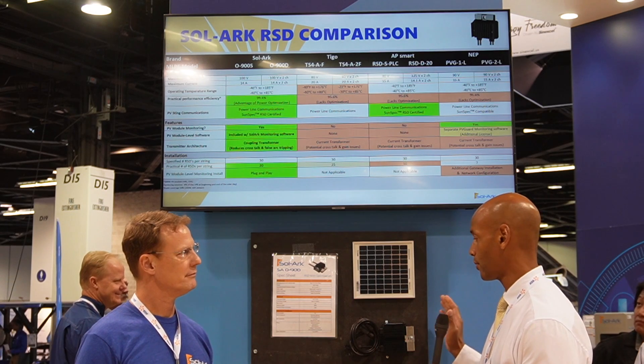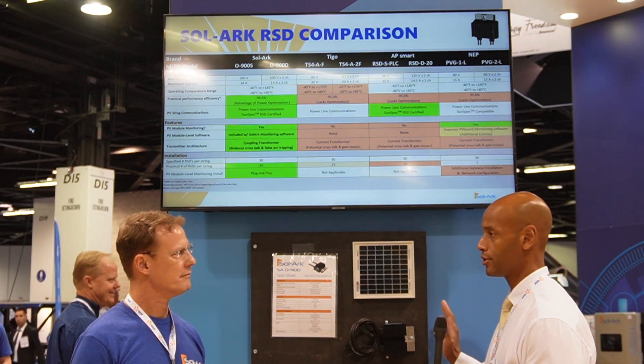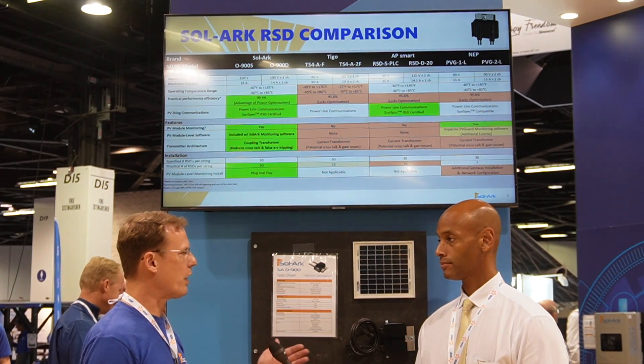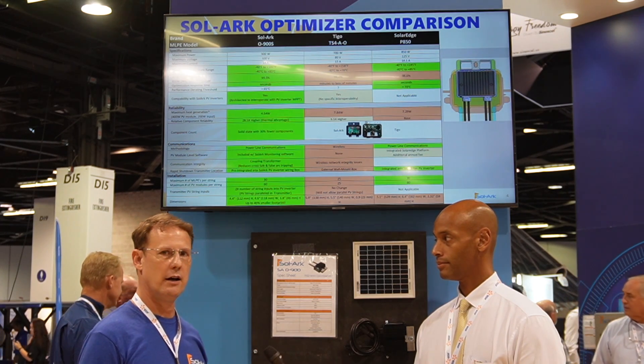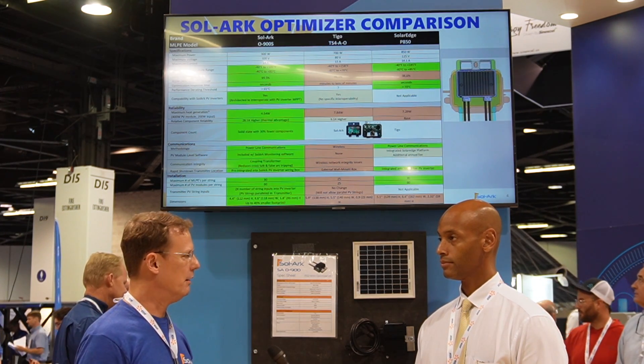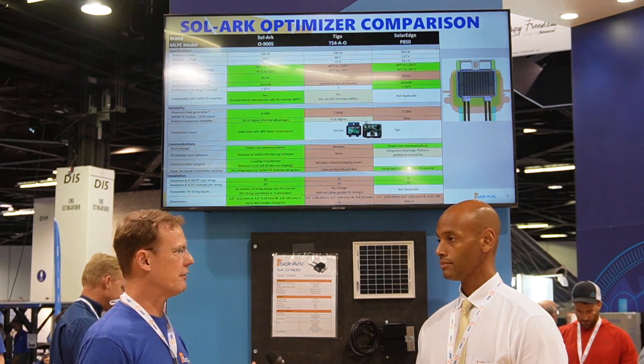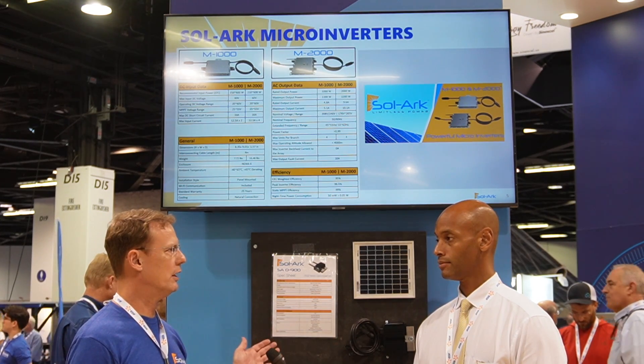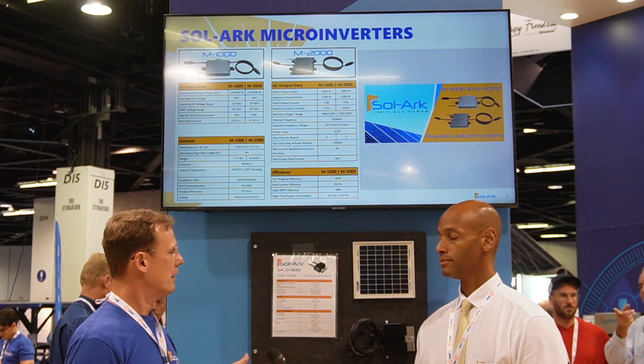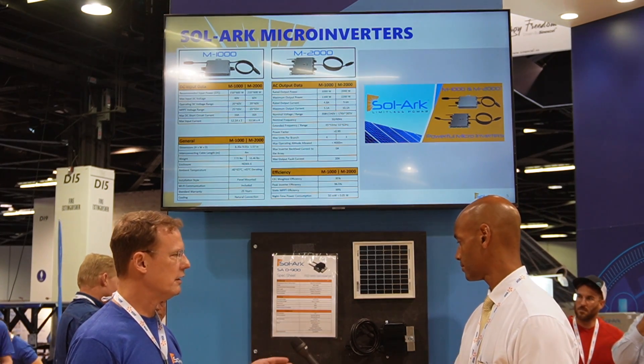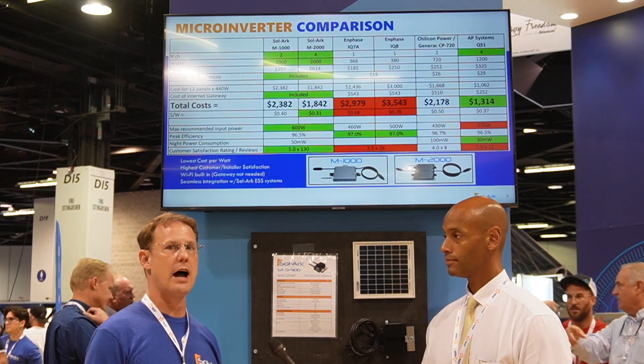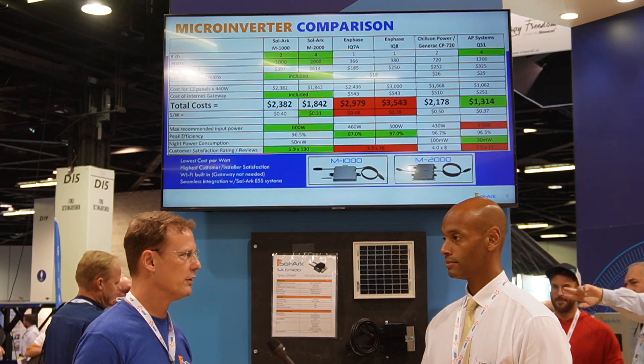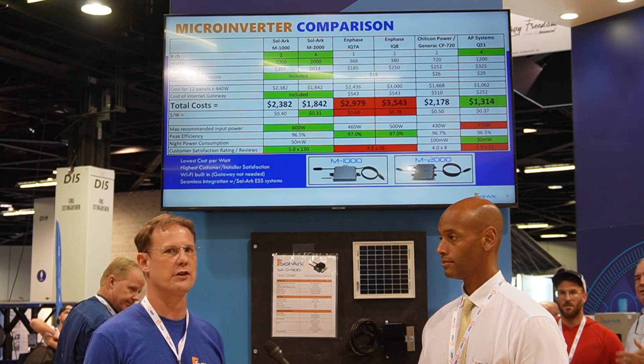Now Tom, is this a requirement for any of the Sol-Ark inverters, or is it purely optional? You do need some sort of rapid shutdown solution for any DC-coupled solar panels to our inverters. You can use other rapid shutdown solutions if you choose — there are several good vendors out there like AP Systems, Tigo, and NEP. What this optimizer adds is monitoring and optimization, which improves power output. It's just an option — one-stop shopping if you're an installer for Sol-Ark.